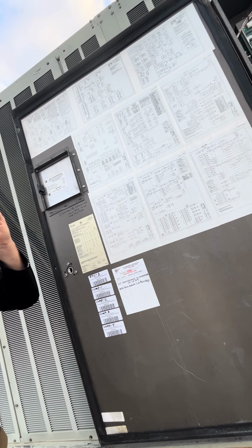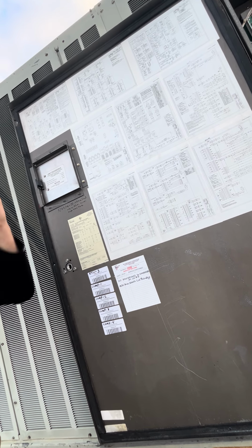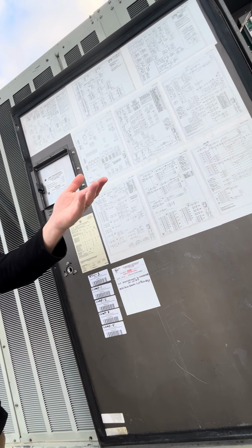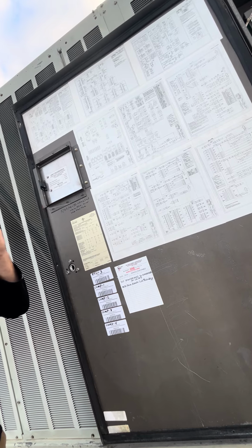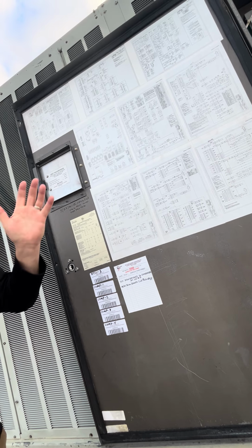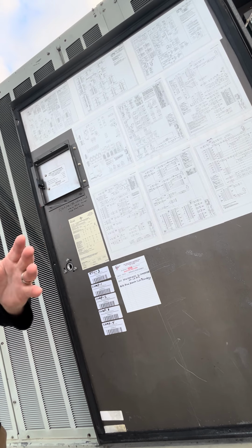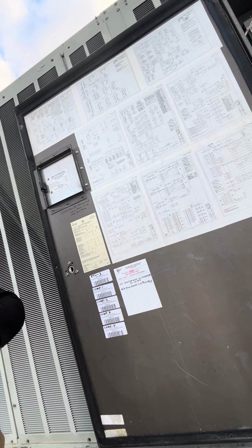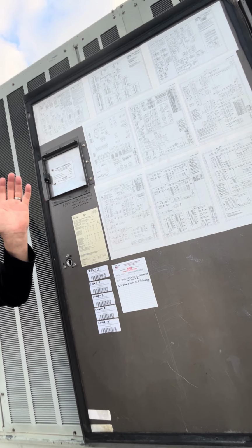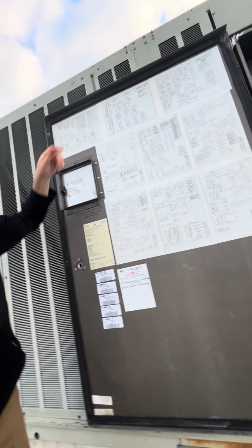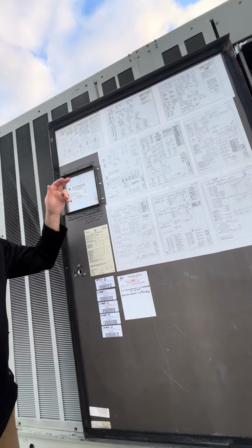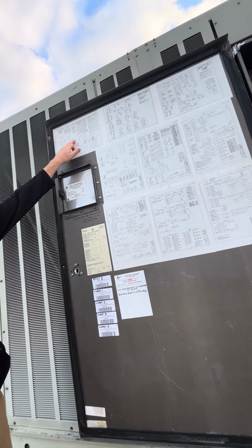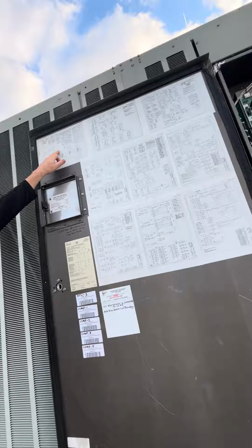We're cooling the space down. The VFD gets slowing down. Our supply temp, which I'll talk about, is going up. The temperature in the store gets down to, let's say, 72 degrees. We say we no longer need mechanical cooling. Click. Now the fan will keep running, but we turn the cooling off. Gotcha. That's what we use that for.